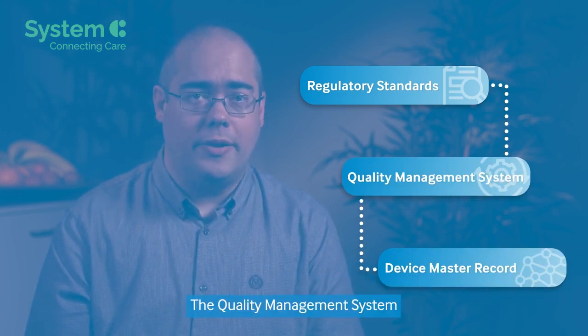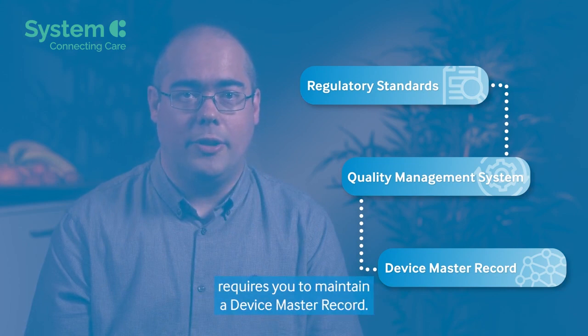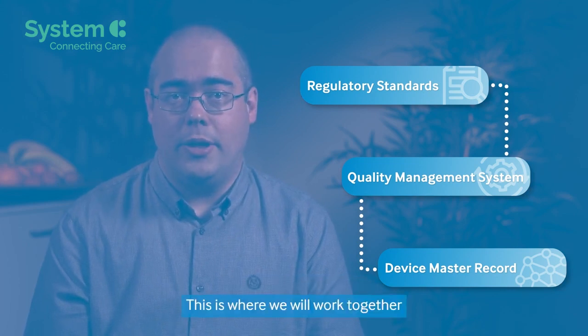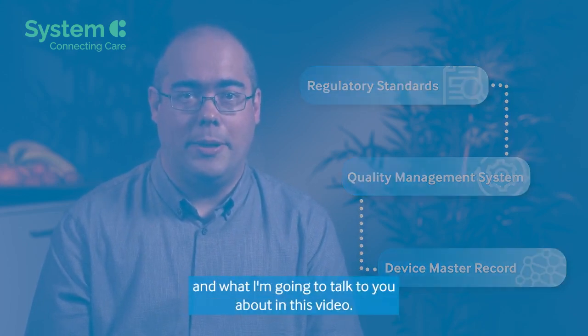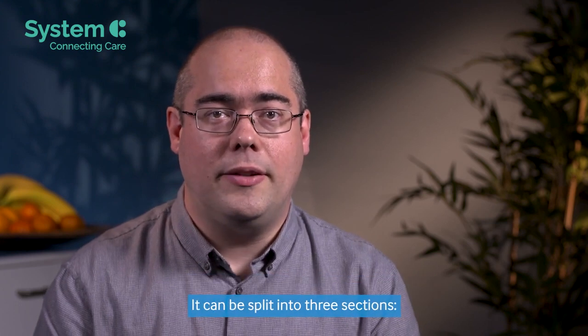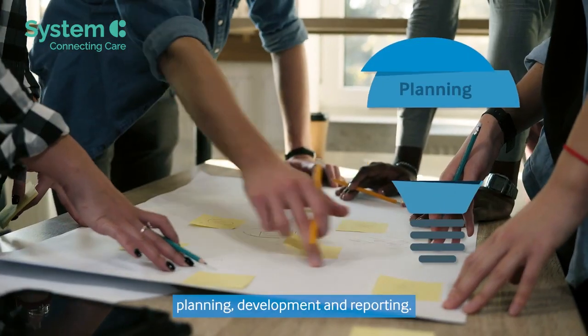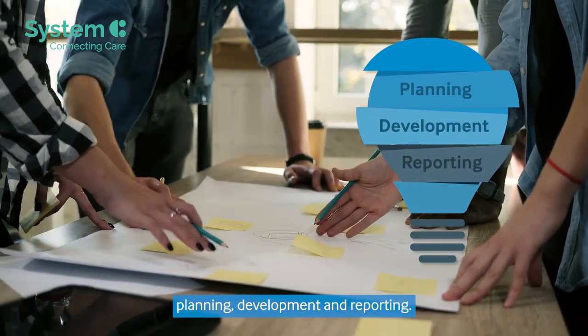The quality management system requires you to maintain a device master record. This is where we will work together, and what I'm going to talk to you about in this video. The device master record documents your plans and the execution of these plans. It can be split into 3 sections: planning, development, and reporting.